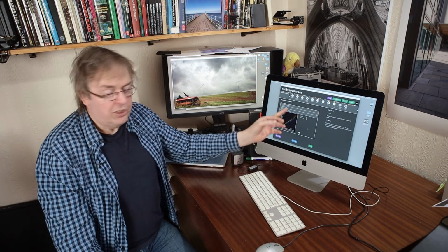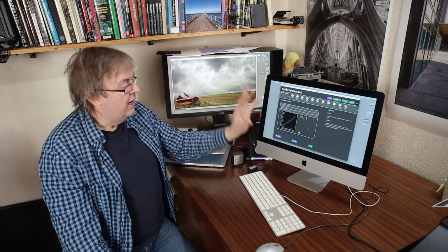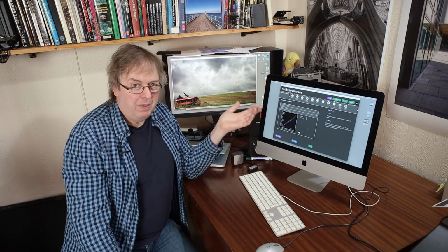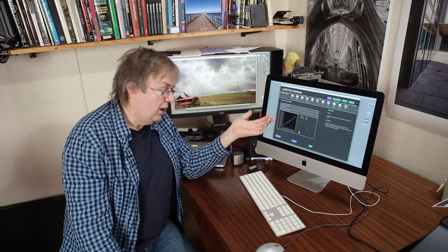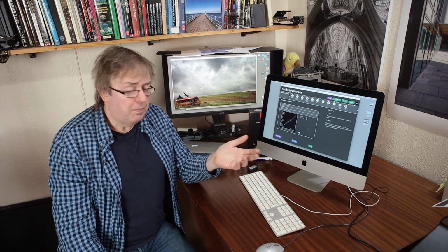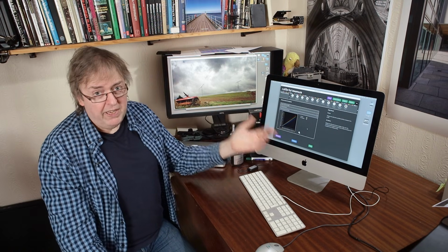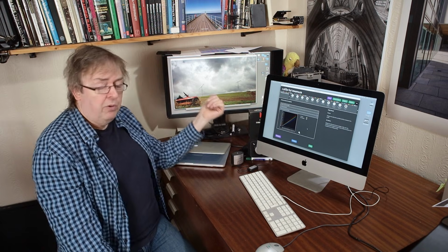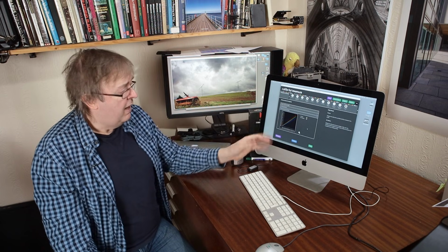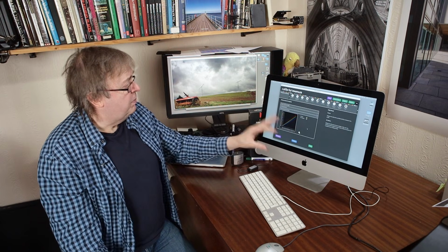And already the divergence of these lines here shows me that this monitor is being pushed to work at 5000, which is no more than I'd expect. You don't get monitors like this for that. If you need to work at color temperatures like that, you get one that can be adjusted separately. So there we go. That tells me it's working, and that's it done.